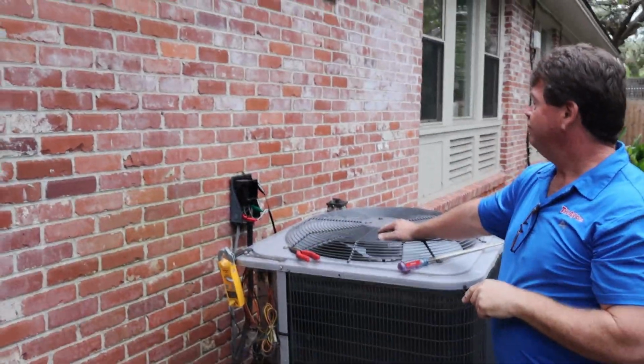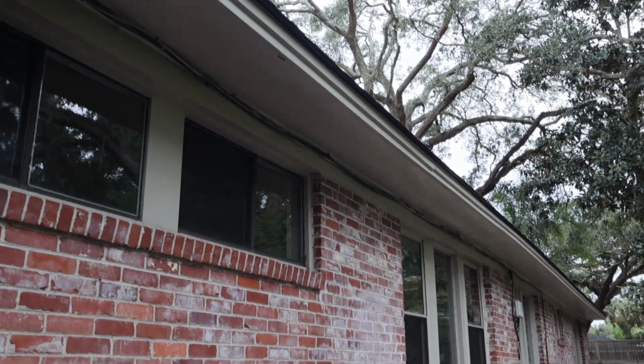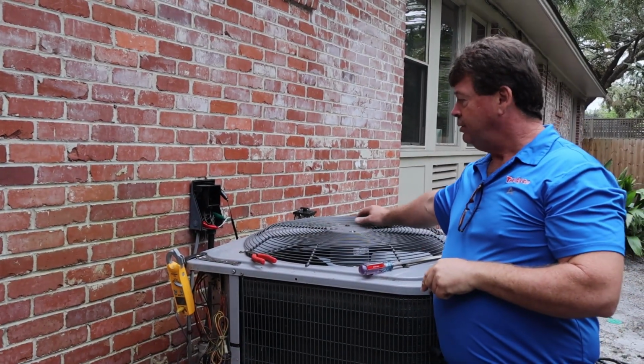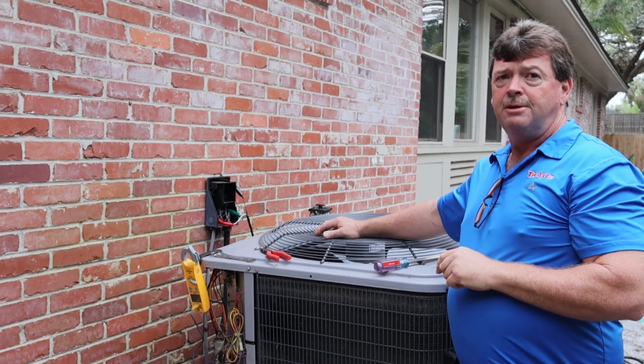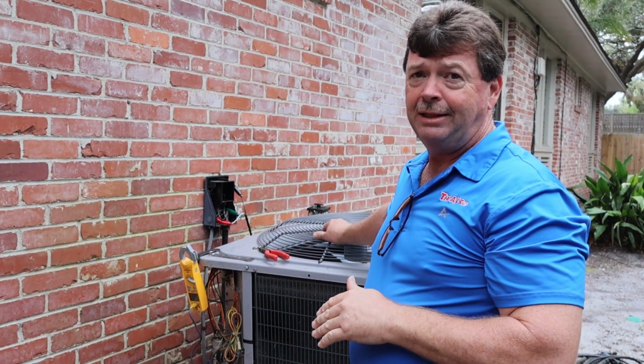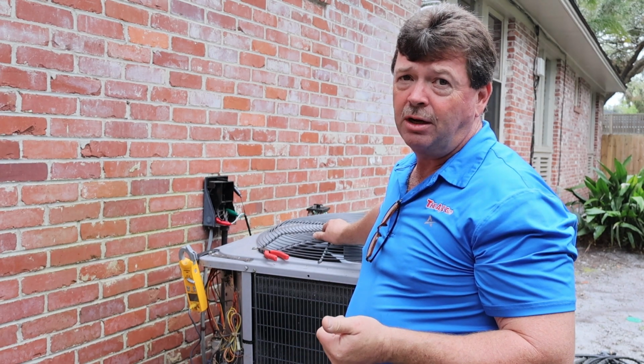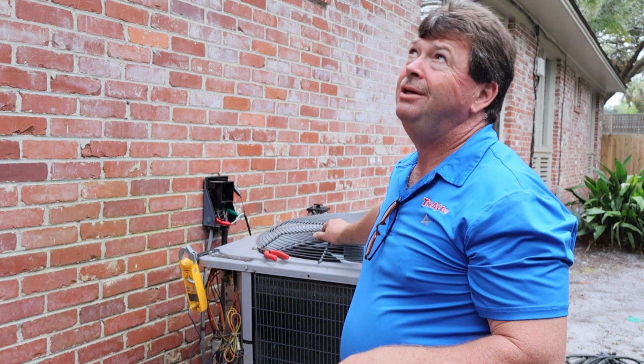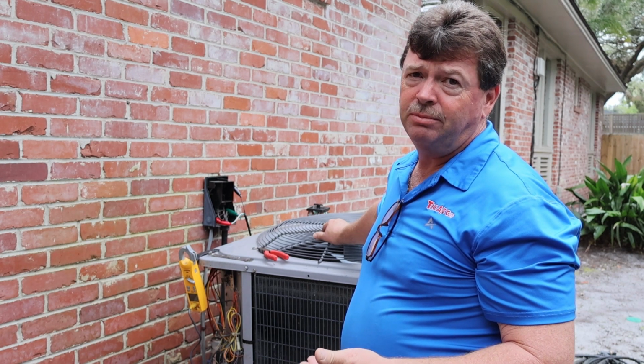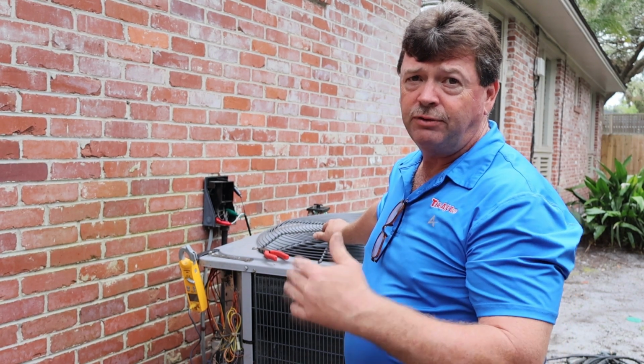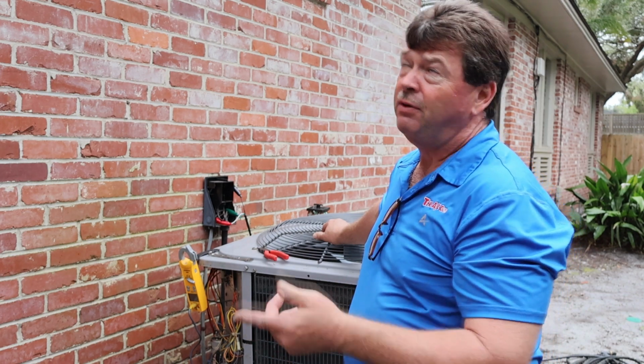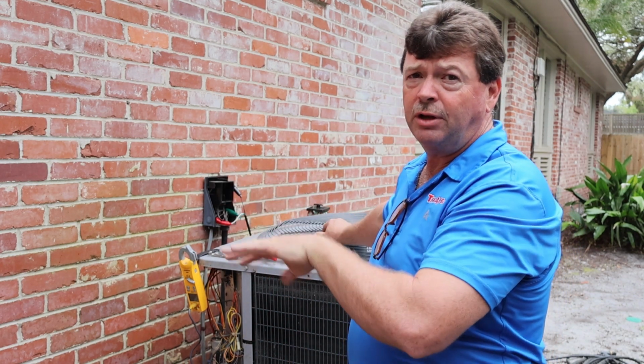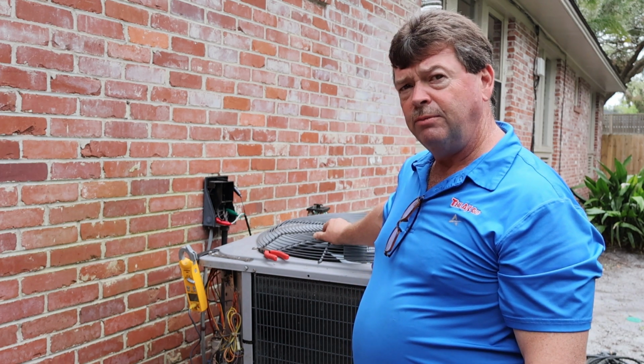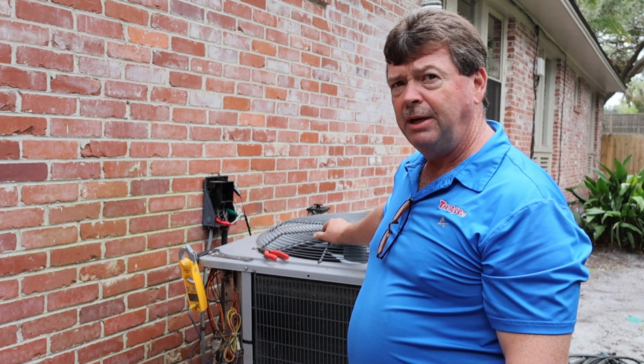See how the eave is right over the condensing unit? If you notice the condensing unit, where it's located, water coming off the roof will drain right into this condenser. Manufacturers don't recommend this, how much harm it causes over time. It's debatable, but it's always good to let the customer know to keep water from just draining off the roof into their machine. You can put a diverter up there and move the water to the right or the left of the machine to keep the water from draining in it. So just something that you probably need to make the homeowner aware.